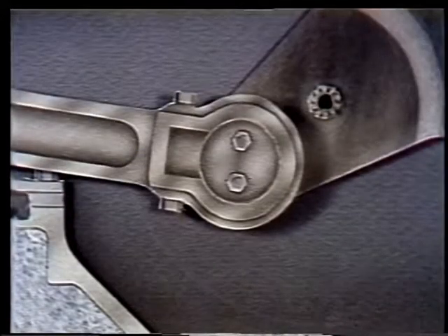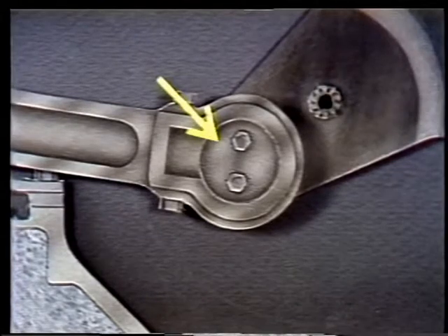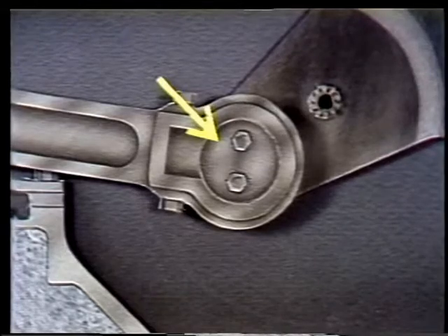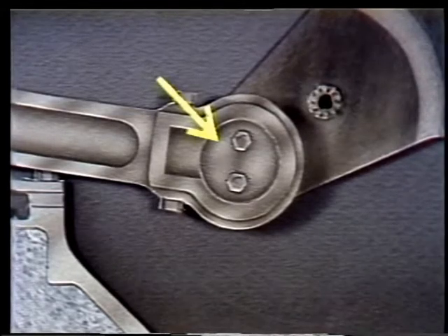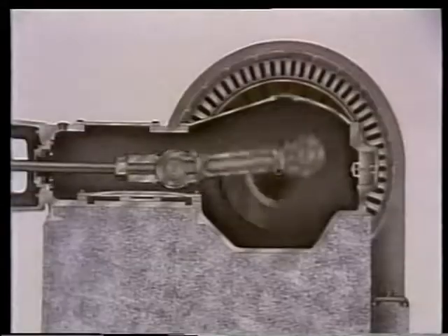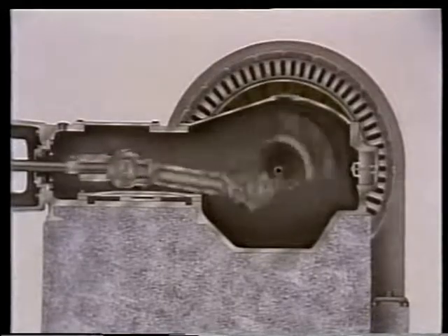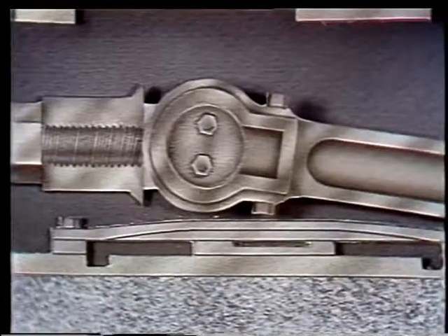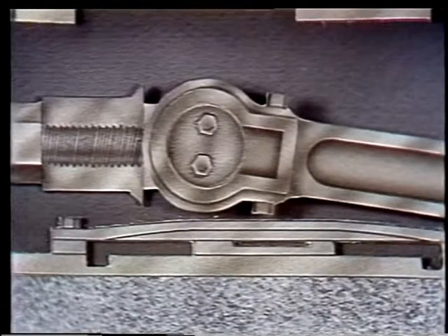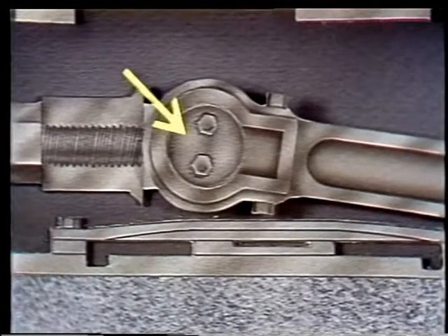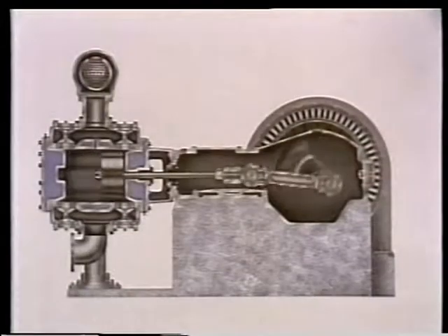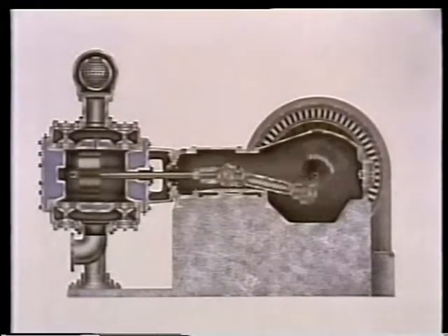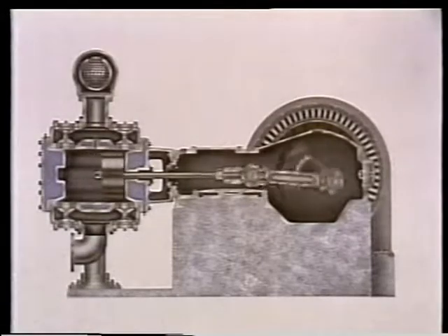The counterweight assembly has a crank pin opposite its main mass. The crank pin and its retaining plate attach the connecting rod to the counterweight, making the connecting rod move back and forth with a swinging, reciprocating motion as the counterweight rotates. The other end of the connecting rod rides on a pin on the crosshead. The crosshead changes the swinging, reciprocating connecting rod motion to a straight, back-forth reciprocating movement.